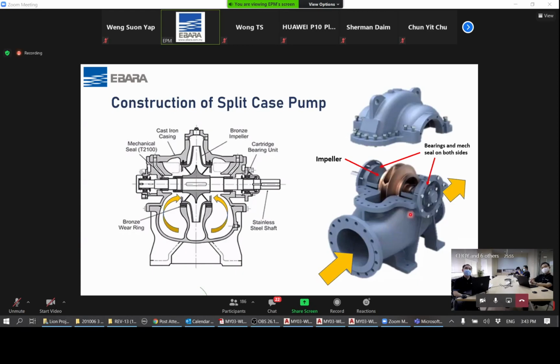The pump casing is usually made out of cast iron, and the impeller could be from bronze or even in some cases stainless steel. And this pump, one of the unique features is that it has a double suction design.